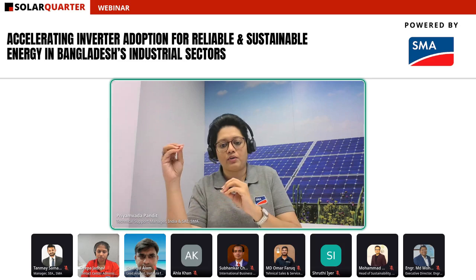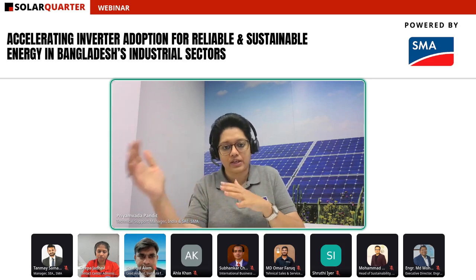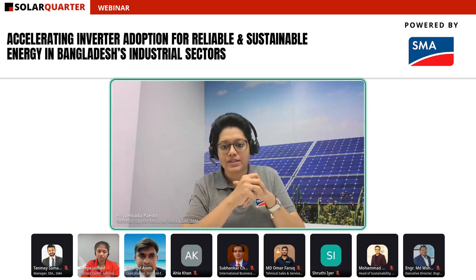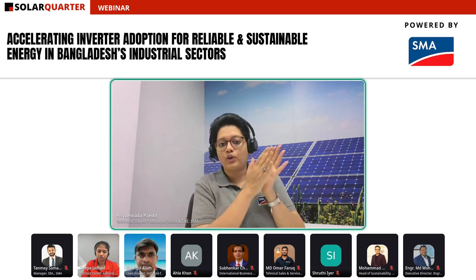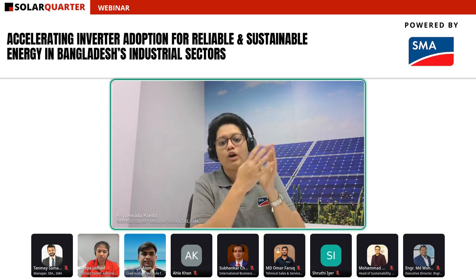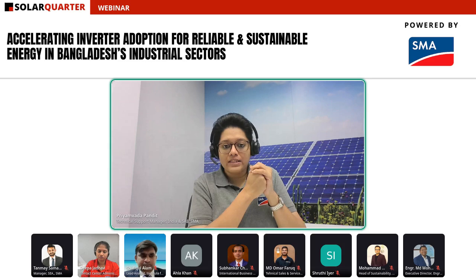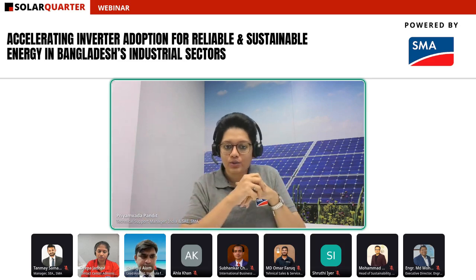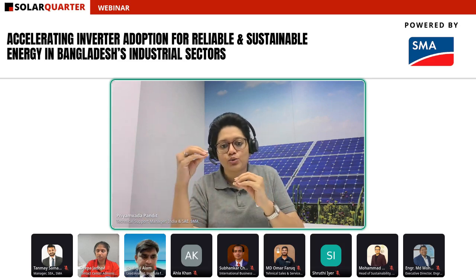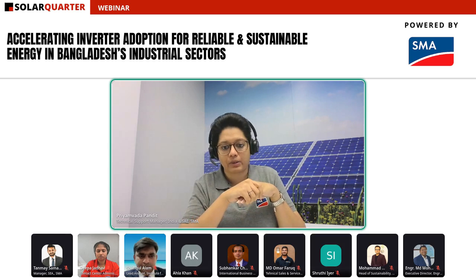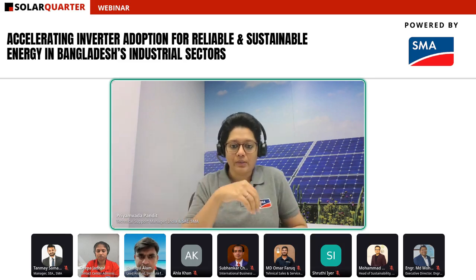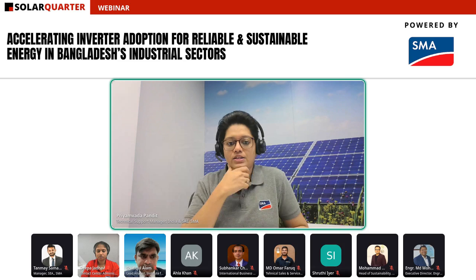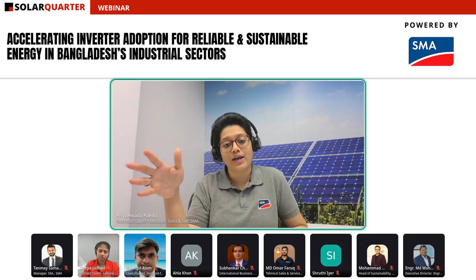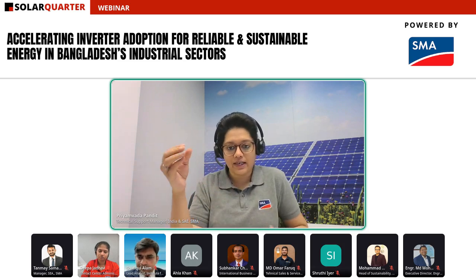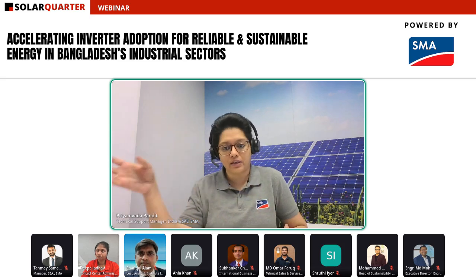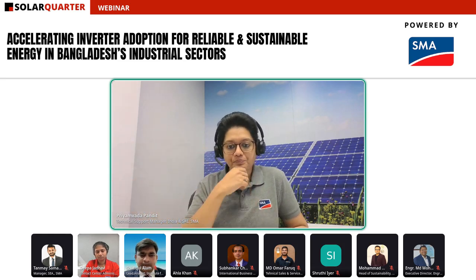As long as your voltage and frequency, if it is a grid-connected inverter, are within the operating limits, it will generate depending upon how much you have on the DC side, how much solar is available. So somebody needs to give feedback to the inverter on how much you need to generate at any specific point in time. That's why you need feedback, and all these parameter settings need to be done in the inverter. You don't require any specialized equipment for that, apart from the inverter and a meter, typically, to give feedback.